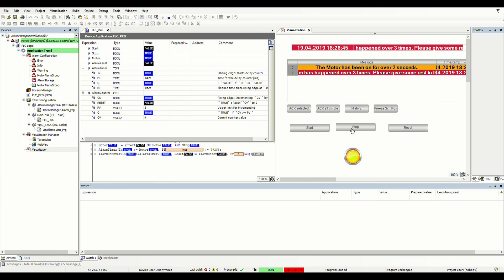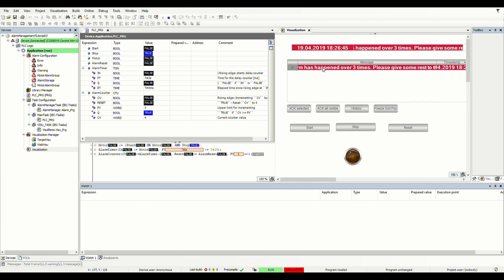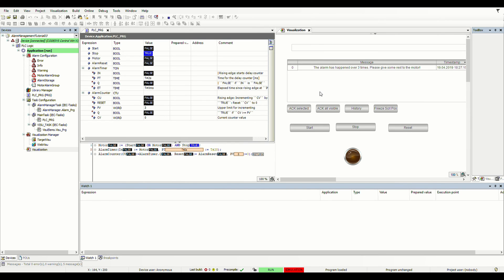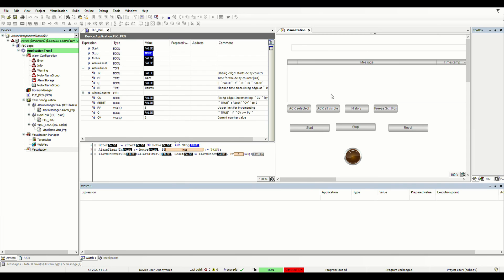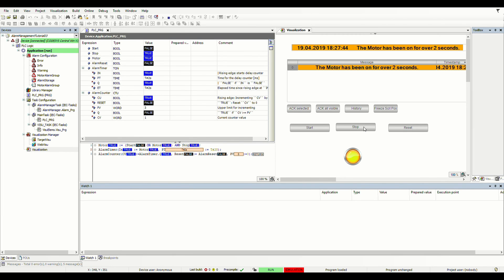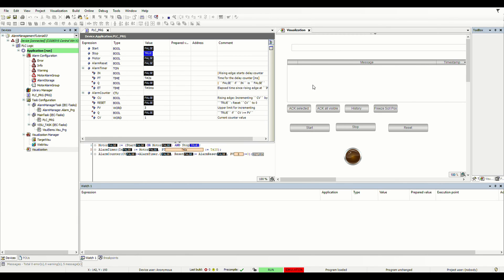Pressing the stop button will stop the motor, but we still have the alarm condition present because we haven't reset the counter. To reset the error, we press the reset button — the counter will reset and the alarm should disappear. However, it is waiting for acknowledgement from the user: clicking the alarm and then pressing Acknowledge Selected will make the alarm disappear. This error alarm is a little different from the warning alarm, which I'll explain in a moment.